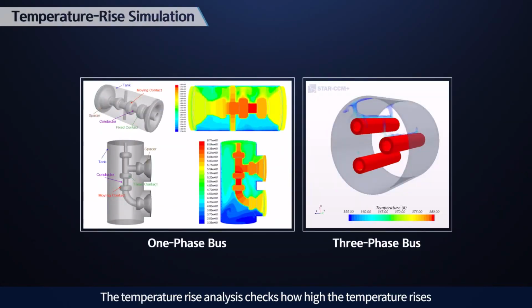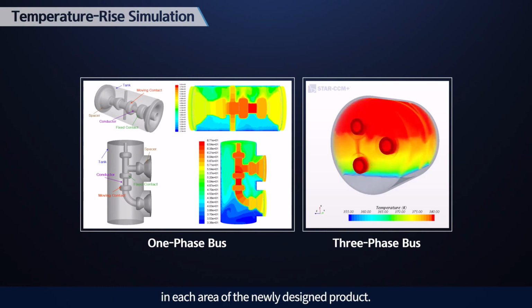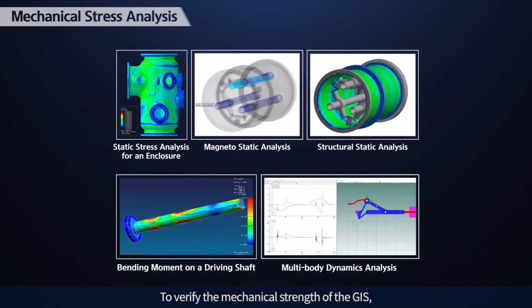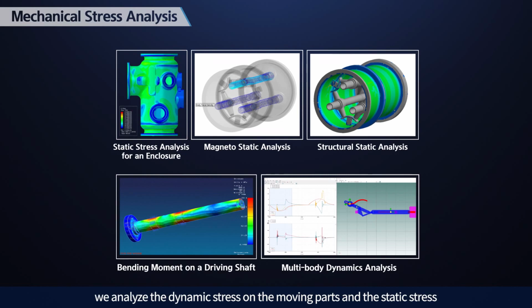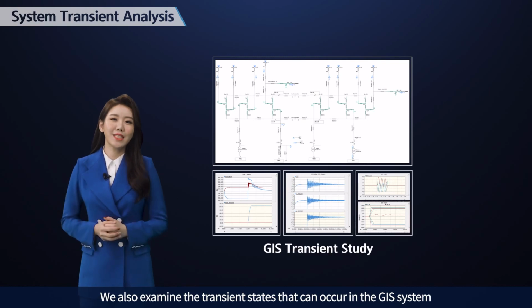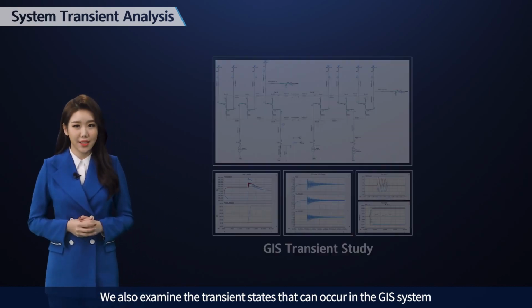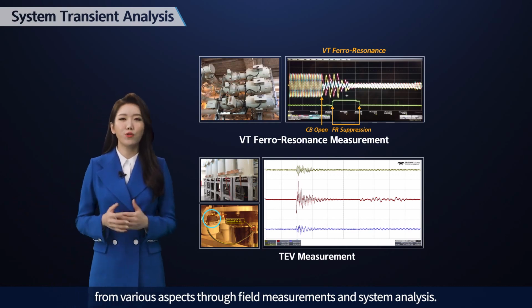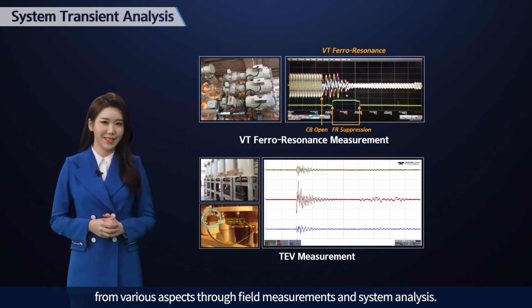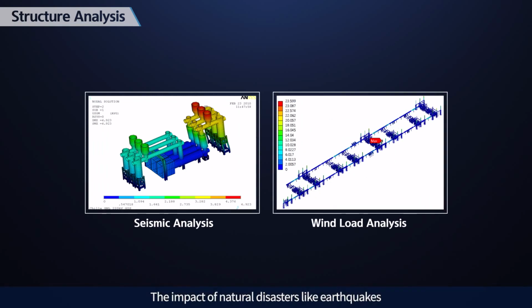The temperature rise analysis checks how high the temperature rises in each area of the newly designed product. To verify the mechanical strength of the GIS, we analyze the dynamic stress on the moving parts and the static stress applied to the components by electromagnetic force and gas pressure. We also examine the transient states that can occur in the GIS system from various aspects through field measurements and system analysis. The impact of natural disasters like earthquakes and other vibrations on the GIS is analyzed as well.